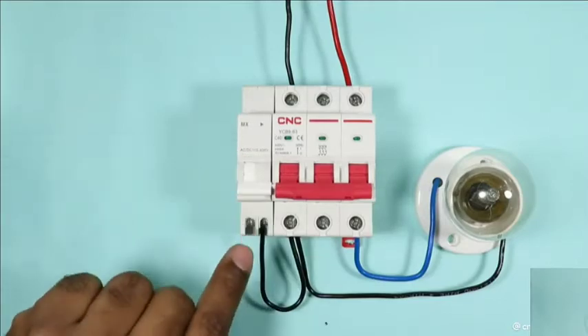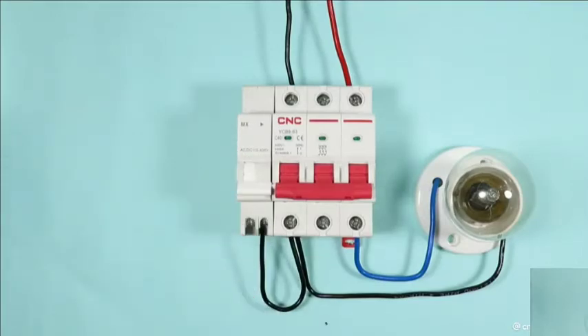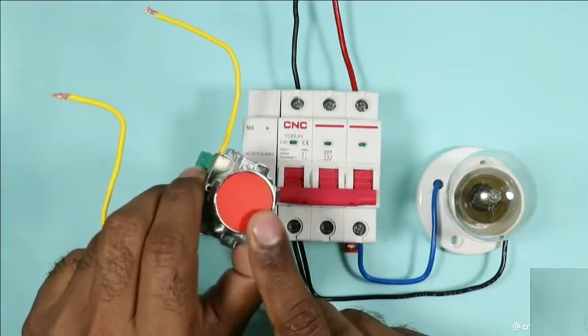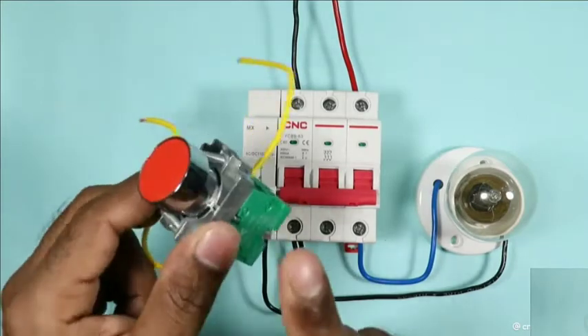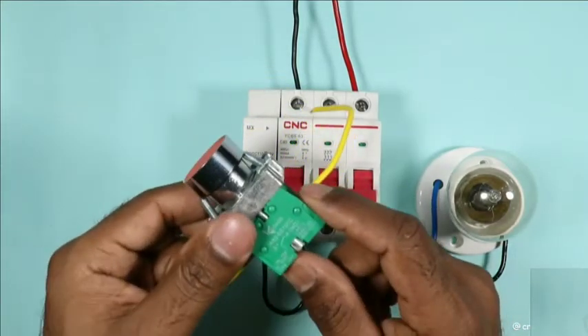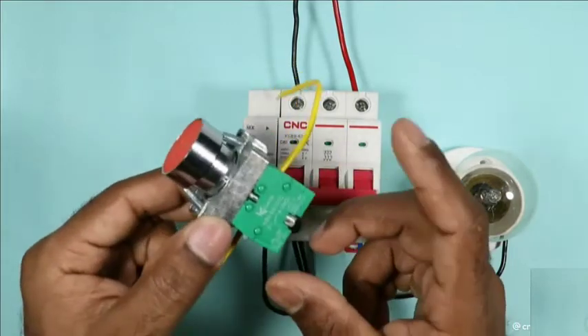In this second terminal of shunt coil, you have to provide phase supply. You have to use this type of push button and the contact used below the push button must be NO contact, means normally open.